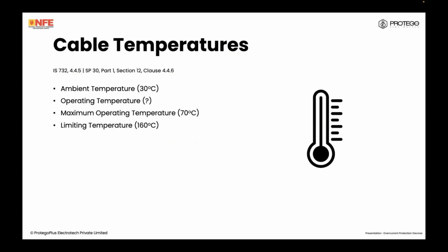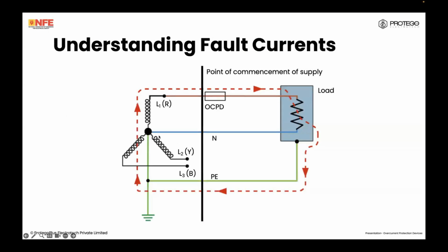When we talk about these temperatures, we assume an ambient temperature of 30 degrees. That is what the cable is at under no load, depending on the surrounding temperature. The operating temperature is, say, if the cable is loaded to a certain percentage of its current carrying capacity, it runs at a certain value. The maximum operating temperature is 70 degrees. The limiting temperature is what temperature the copper inside the cable, and hence the insulation, will achieve in this 0.1 seconds. This is 160 degrees Celsius for our PVC cables.